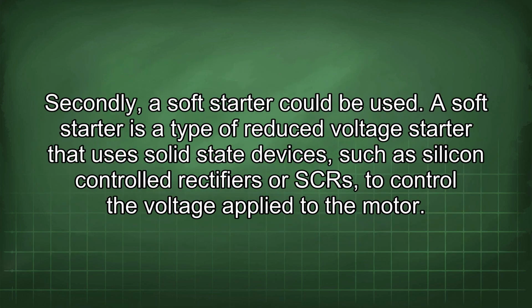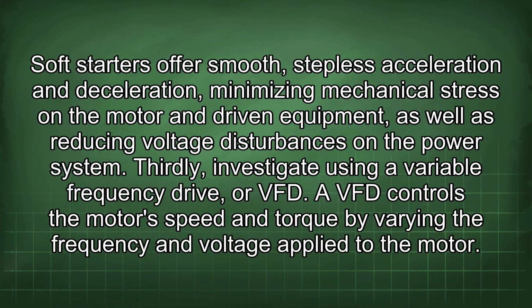Secondly, a soft starter could be used. A soft starter is a type of reduced voltage starter that uses solid-state devices, such as silicon-controlled rectifiers, or SCRs, to control the voltage applied to the motor. Soft starters offer smooth, stepless acceleration and deceleration, minimizing mechanical stress on the motor and driven equipment, as well as reducing voltage disturbances on the power system.